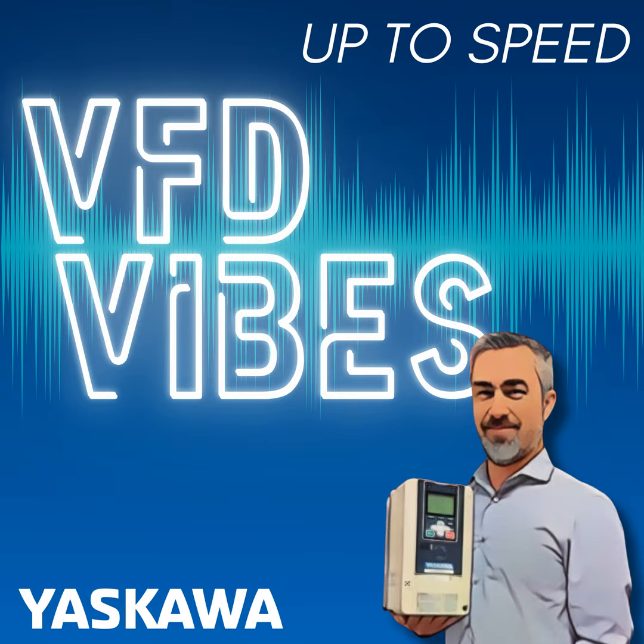And if you want to find where the square root of 3 comes from, go look at Wikipedia for three-phase systems. There's a whole derivation on the RMS voltage versus peak and all that, but we are not diving into that. No, we're not an audio podcast. But it does point out the distinction between what we call line-to-line voltage, which is 480. We would call that a 480-volt system if the line-to-line voltage is 480 volts. The line-to-neutral voltage will be 277 on a 480-volt line-to-line system.